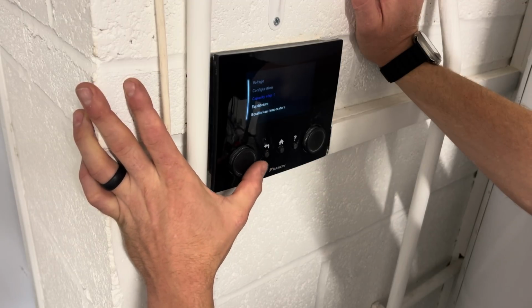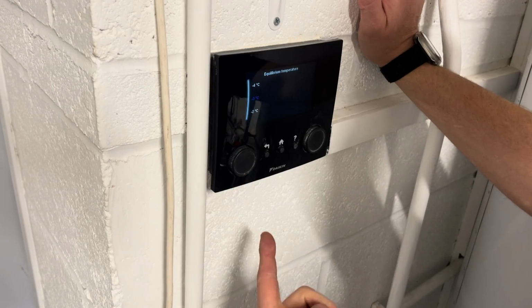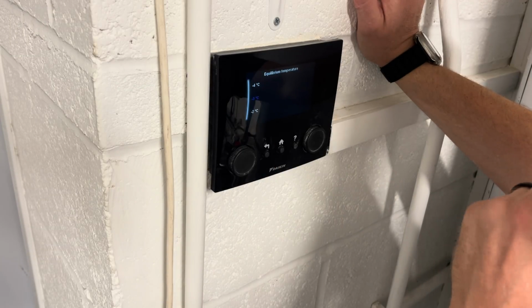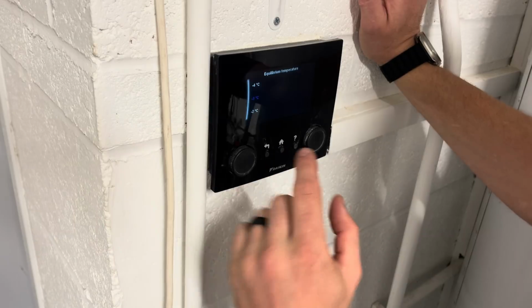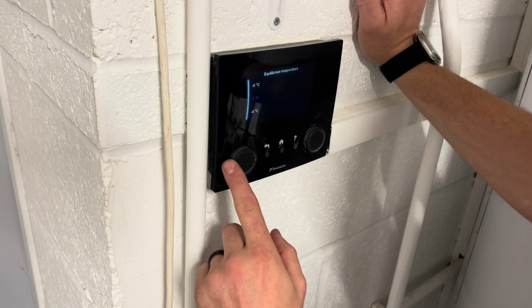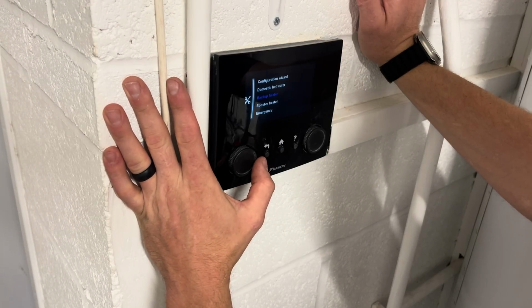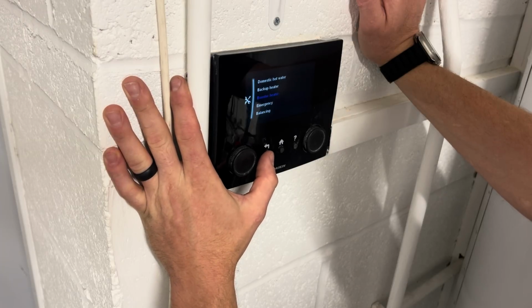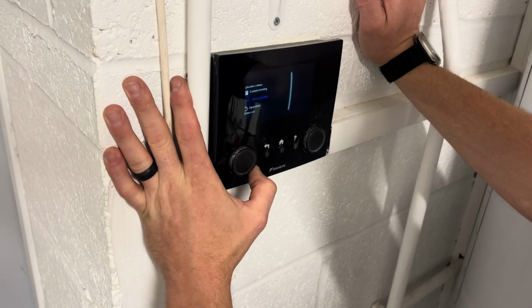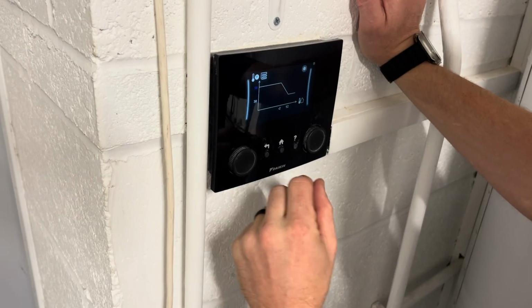The one thing that isn't so bad is the backup heater. Normally the backup heater is set at 0 degrees, so that it comes on at 0 degrees. They've set this to -3, which is fine. It'll probably come on 1 or 2 times a year, but we don't need that to come on at all. It's a 20-year-old house. I'm going to put that to -7. The booster heater is allowed just for the disinfection, and our main problems are the weather curve is at 50.